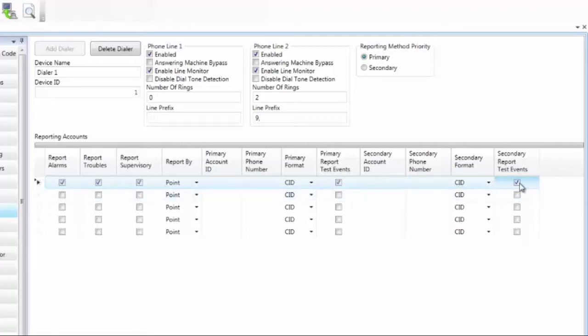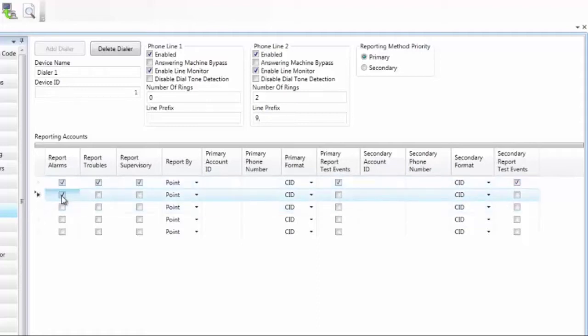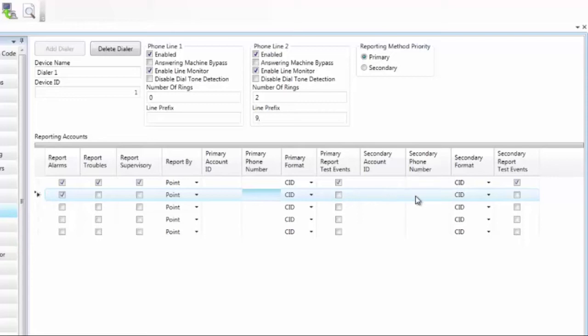So once you fill that information in, that will be going to your central station. Now if you want information to go to multiple locations. So let's say you want it to go to central station and to a security office on site. But you only want the alarms to go to that security office. You go down to the second line and you select alarms. And then you can decide point, panel or zone again. Set up the account number for that particular receiver you're going to. And the phone number that you're going to call to that receiver. And then if there's a backup, you can set up the secondary account number and the secondary phone number.